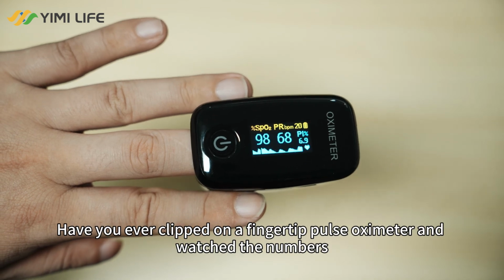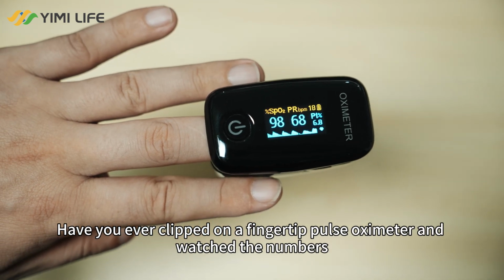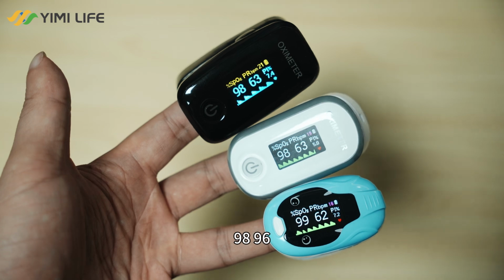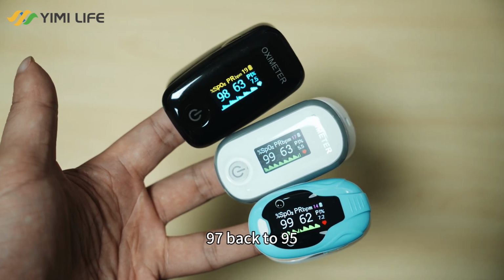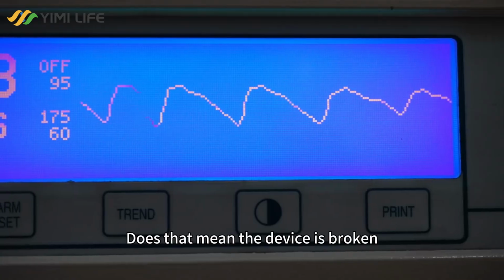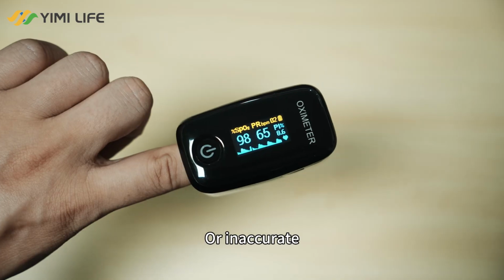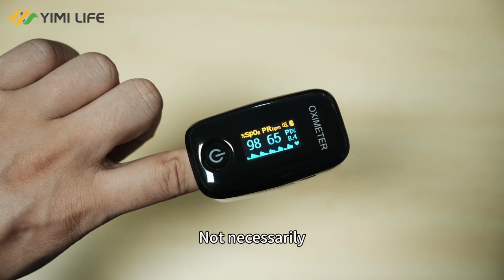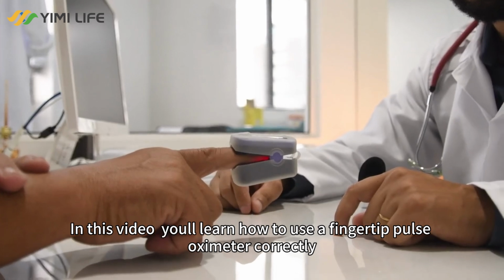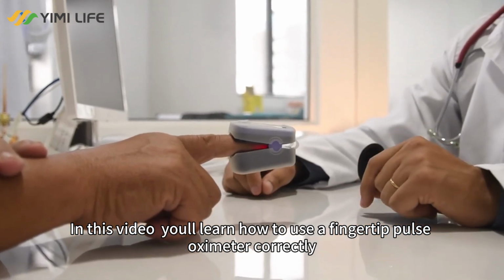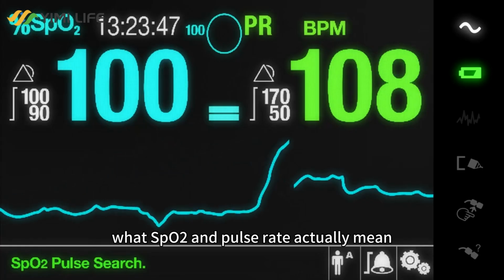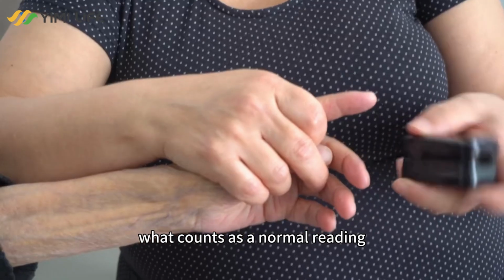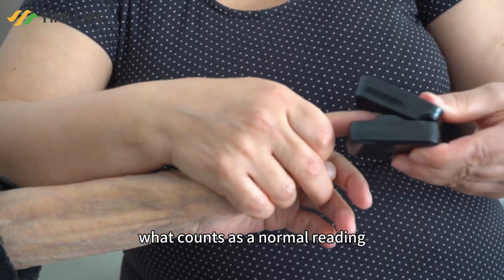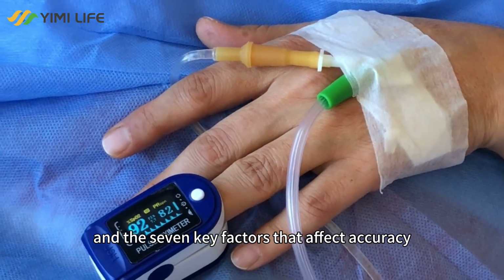Have you ever clipped on a fingertip pulse oximeter and watched the numbers jump around? 98, 96, 97, back to 95. Does that mean the device is broken or inaccurate? Not necessarily. In this video, you'll learn how to use a fingertip pulse oximeter correctly, what SpO2 and pulse rate actually mean, what counts as a normal reading, and the 7 key factors that affect accuracy.